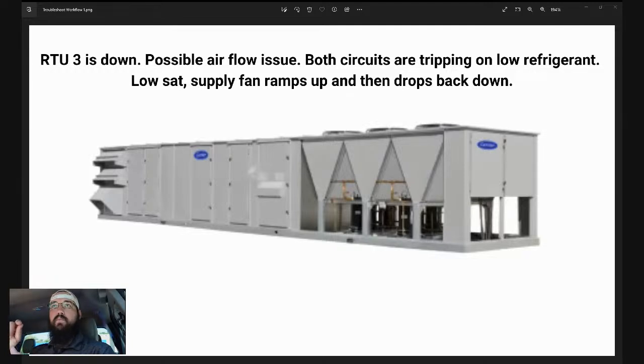If we're seeing some weird fluctuation, which honestly sounds like hunting, then in a hunting scenario the TXV is going to fly way too far open. It's going to flood the coil. It's going to see that and overreact. Then it's going to come back and underfeed the coil, so we see our superheat spike super hard. Then it comes back, then it goes back. Now, a sticking TXV where the rods in there are beginning to fail can cause a very similar condition.